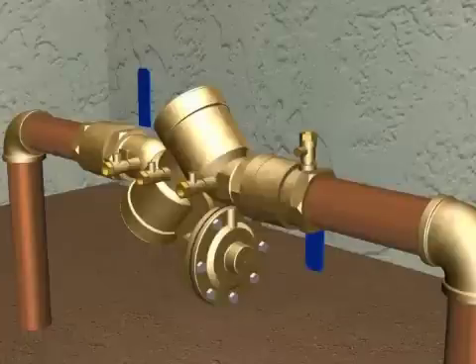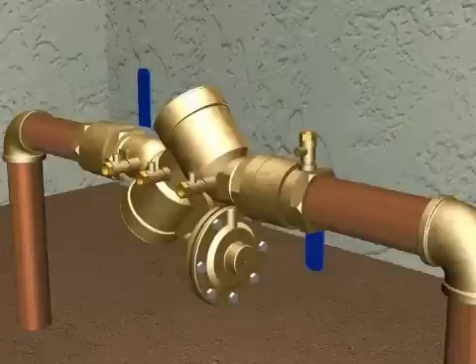You will repeat this procedure on the second check valve. Before servicing the relief valve, you want to make sure to check the troubleshooting section of the instructions. The most common cause of discharge from the relief valve is debris in the number one check valve.